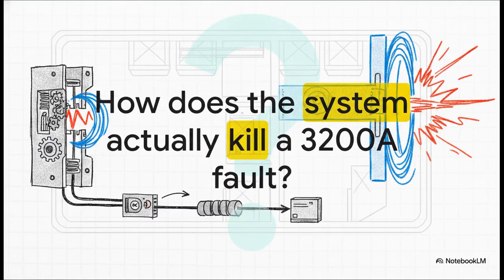You came into this explainer knowing that switchgear is dangerous, and now you understand exactly how those metal-clad firewalls provide real arc-proof survivability. You know exactly why the door-closed racking rule is literally a matter of life and death, and you can identify why a Rogowski coil's linear output is absolutely vital for your protection relays. The sensors tell the system exactly what's happening without saturating.